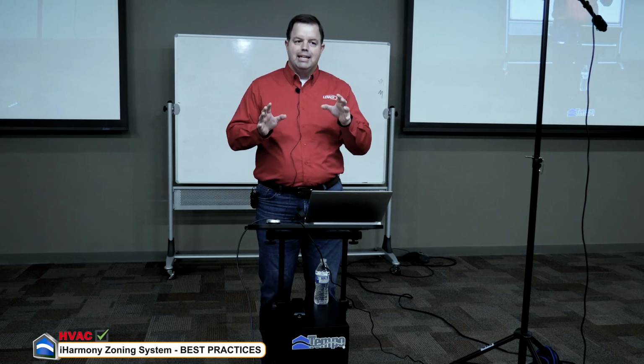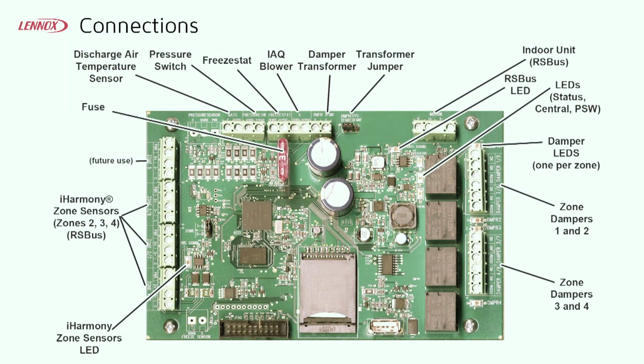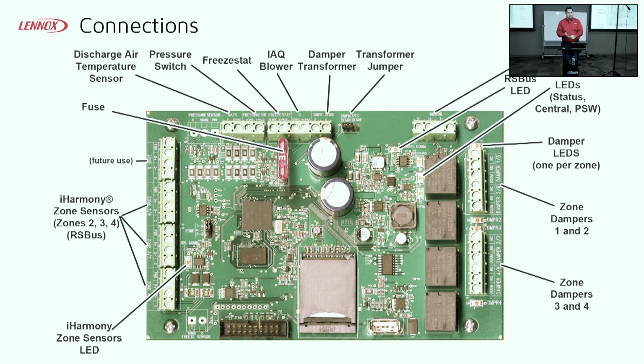But there's so many times, where I tell guys, when you're going out and troubleshooting these issues, we tend to build it up, especially if it's your 3rd or 4th trip out there, where it's like, man, this has got to be a big issue. This has got to be something that no one has ever seen before. But so many times, the first thing I'm going to do is go out there and just look at these basic issues. Is everything wired up right? Is it mounted correctly? Is everything placed where it's supposed to be? Because usually that's where we start having these issues.